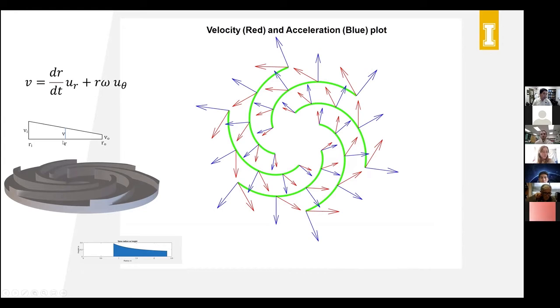And so depending on the flow and the impeller profile, how the velocity along the radial line changes varies a little bit. For this particular design, we assume that the velocity linearly changes from inlet to outlet. And for the velocity to change linearly from inlet to outlet, the profile itself has to be a little bit curvilinear on the top. From the measured data, and with the assumption that the fluid moving through this vane is incompressible, we were able to find the radial velocity and tangential velocity for any pump that we want to design.